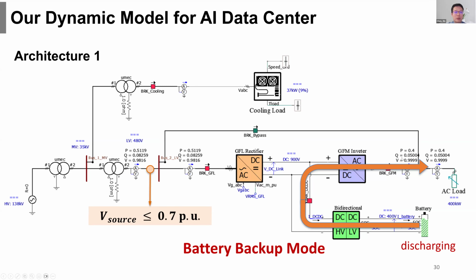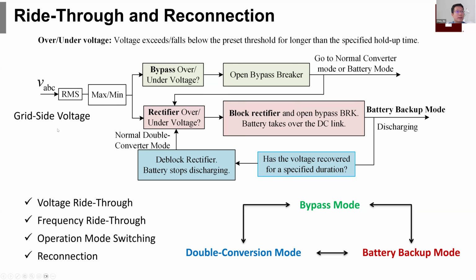In this case, the data center will switch to the battery backup mode, and the battery is discharging to supply the AC computing load going through this path. It's going through the DC-DC converter and through this grid forming inverter and then connected to the AC load power. The mode switching between these three operation modes is critical for the data center response to the grid side disturbance and also their dynamics. So in our model, we have implemented and embedded the ride-through mechanism and all those mode switching logics into our model.